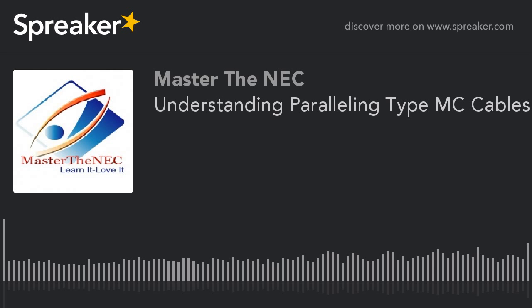So let's take it one further. Let's say we're going to create some 3/0 MC cable. The conductors are copper and they're 3/0. What size equipment ground would we have to have? We're talking about a single cable now. Well, basically you go down the column, it's Table 6.1, and it says 3/0 through 250 kcmil requires a size 4 copper equipment grounding conductor. All right, so that is what you're going to see in the product. We're going to give you 3/0 conductors, and we're going to give you a 4 equipment grounding conductor, and that's what you're going to get. And that's the minimum standard here for 90° insulated conductors.